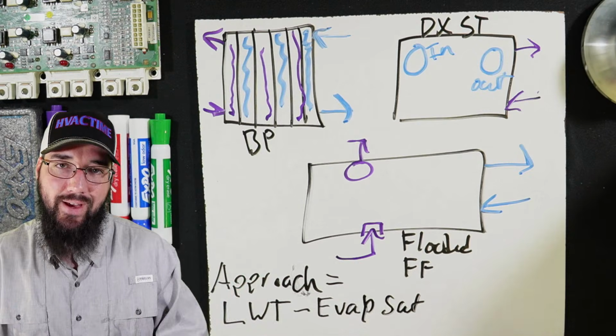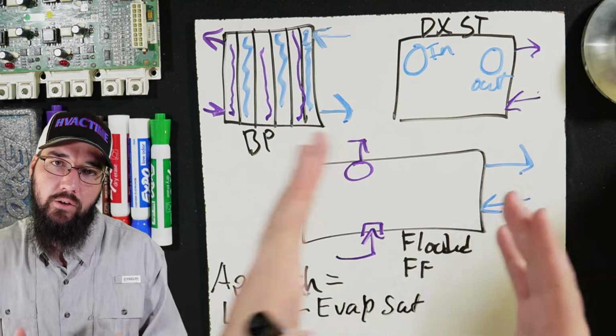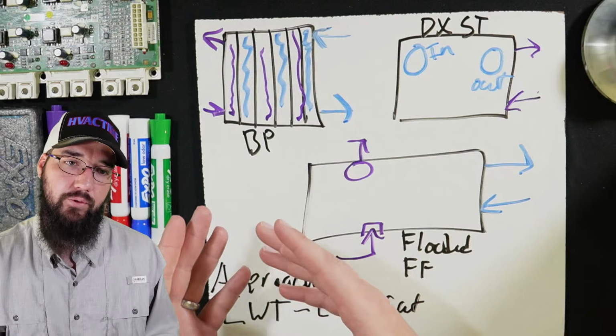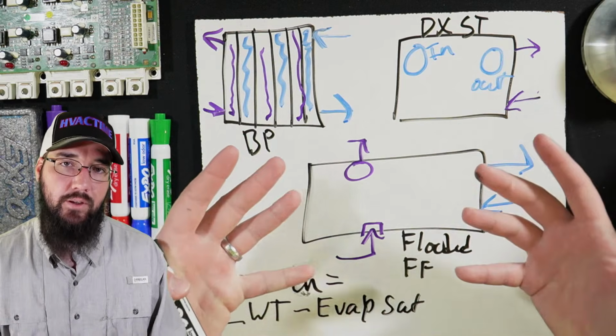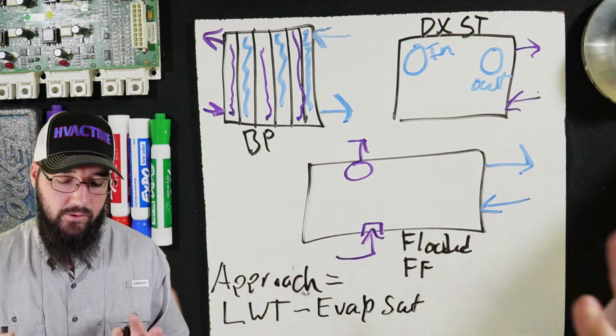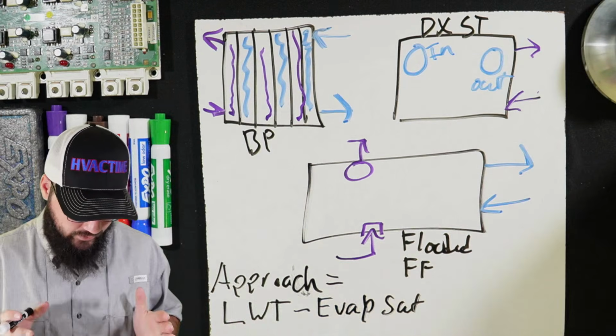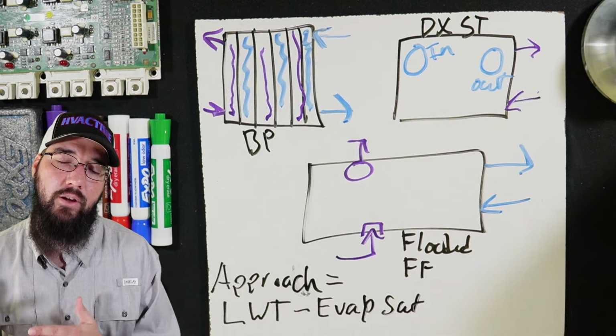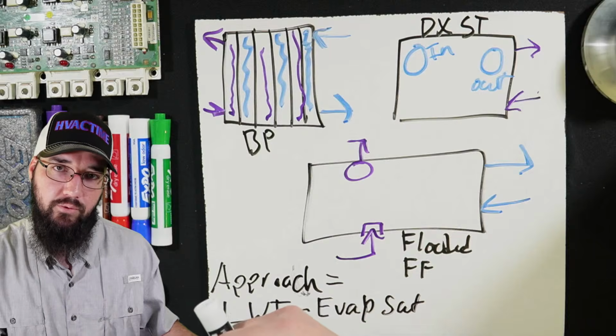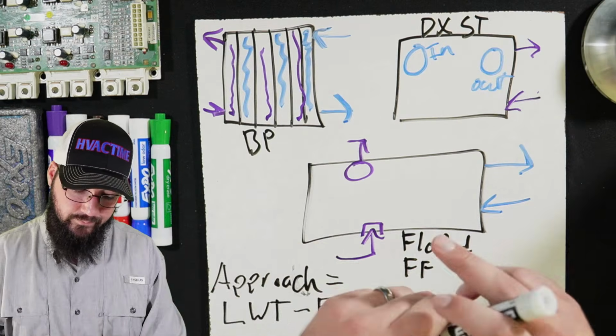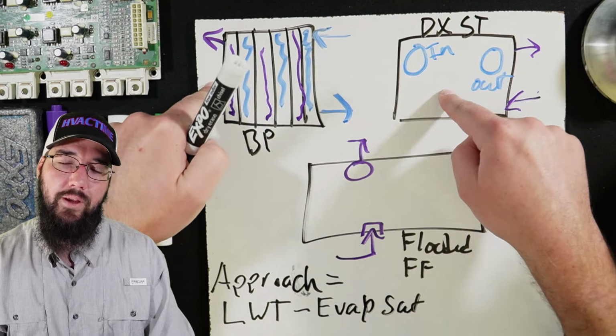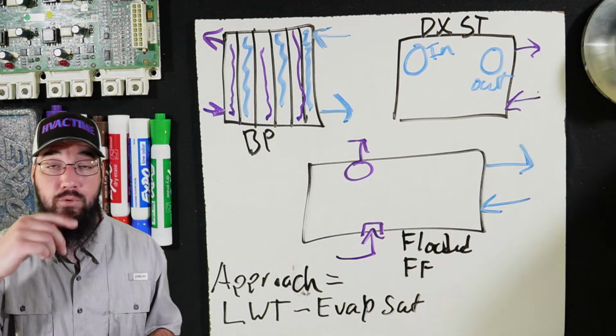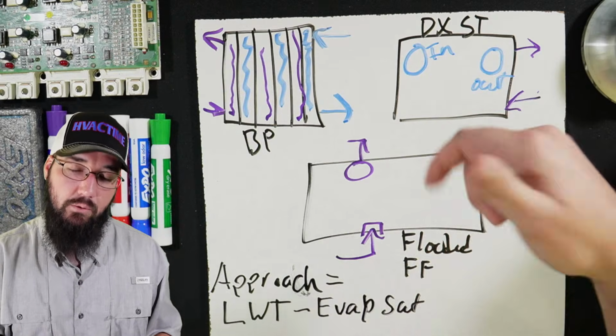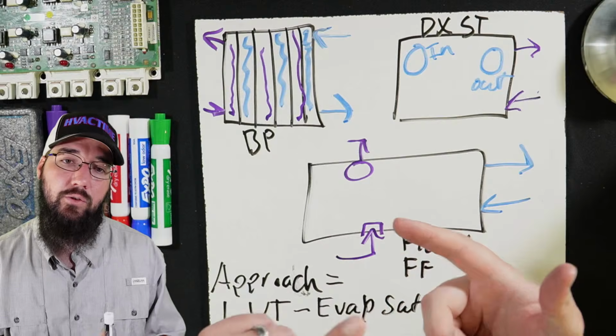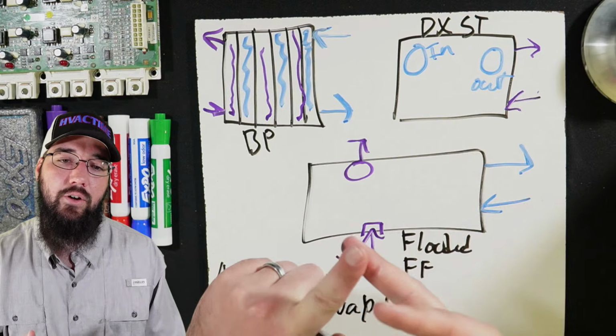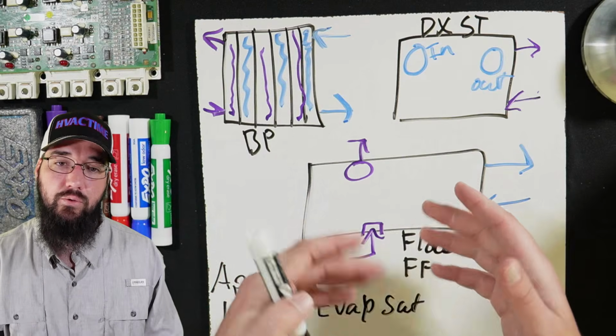We're measuring how effective, how well we're transferring heat from one to the other, from the water side to the refrigerant specifically. This can be flipped and inverted for the condenser side. We can say it, but it's just for simplicity today. How well are we moving heat from water into the refrigerant? Now, these two are less efficient. We can tell that because they run higher approach values. They just don't do as well, but they require less refrigerant. They're cheaper in that way, as you don't have to put as much refrigerant into the machine. And from my understanding, they're cheaper to manufacture compared to these styles here.